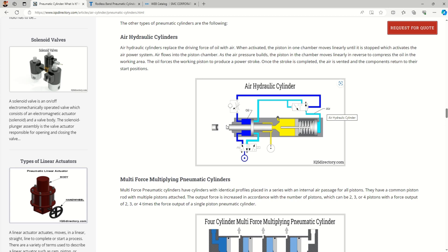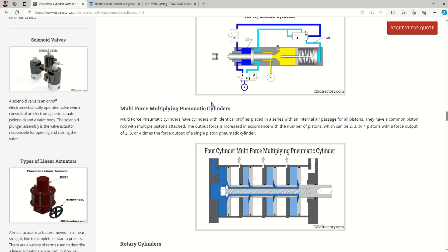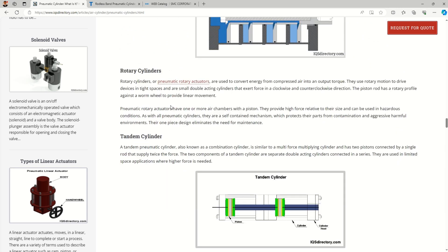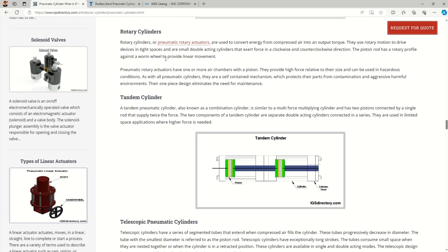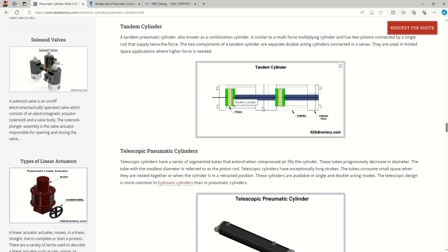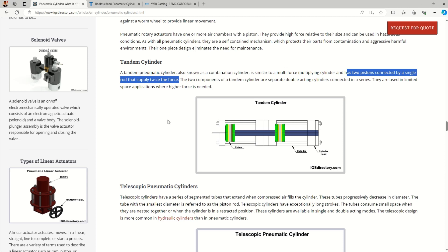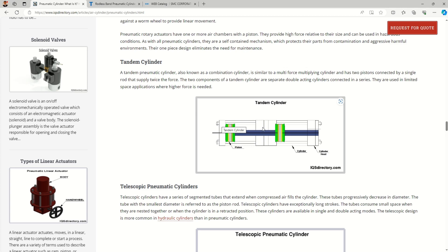Multi-force multiplying pneumatic cylinders multiply force within a compact size — they are like different cylinders connected in series. Rotary cylinders are used when angular motion is required. Tandem cylinders combine two cylinders in series with two pistons on a single rod, supplying twice the force. This makes tandem cylinders useful when you need larger forces in a compact space.